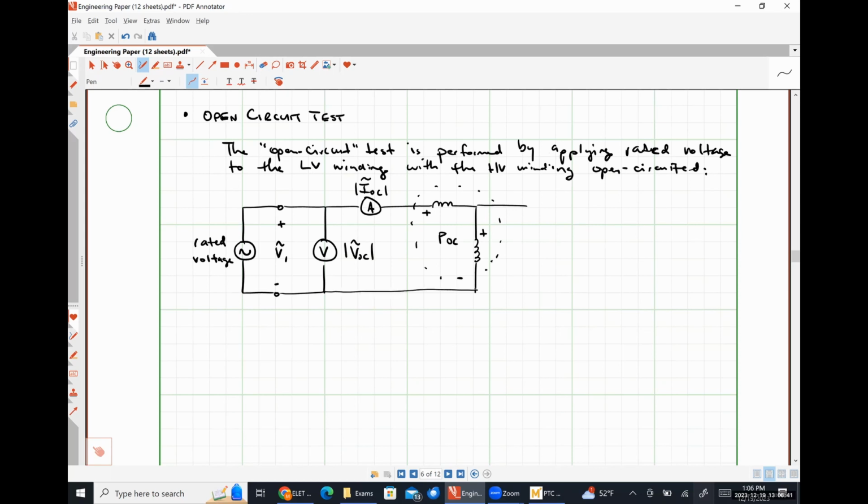And then now that we have all of our measurement network set up, we'll connect this to our transformer. Where I'm going to call this NHV to let us know specifically. And that's wrong. This is supposed to be the low voltage side. Getting that backwards. And then over here, this will be our high voltage side. That is left open circuited specifically.